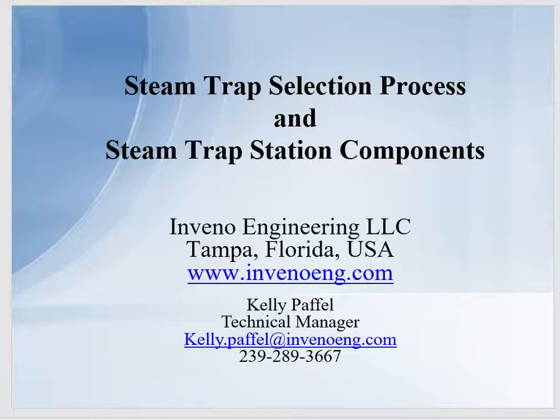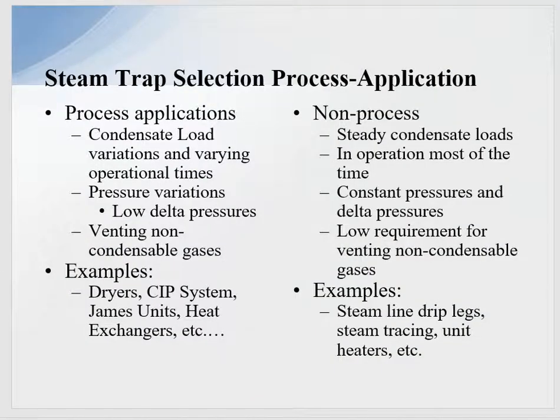The selection process is quite simple. We have steam trap selection process by application — we want to simplify it by application. The application considerations include condensate load variations and varying operational times. Condensate loads can be very low, 100 pounds per hour, and then increase up to 4,000 or higher pounds per hour. They can be in operation for 2 hours a day or 18 hours a day.